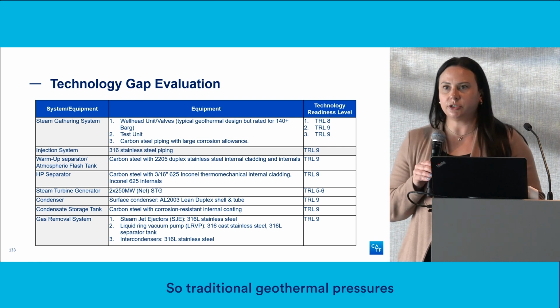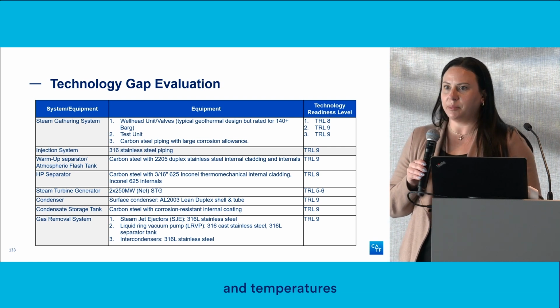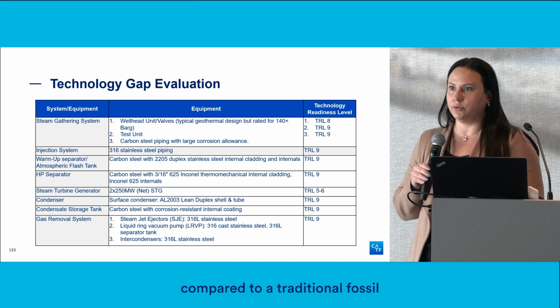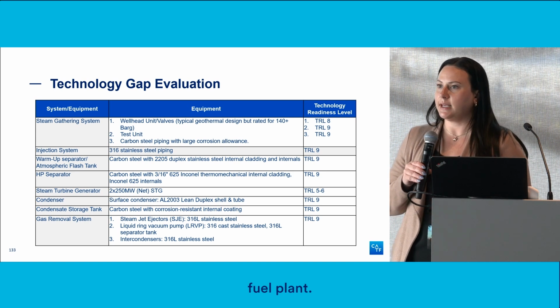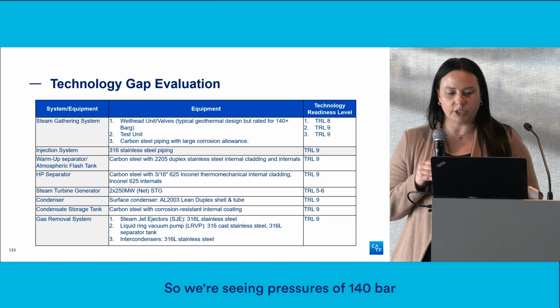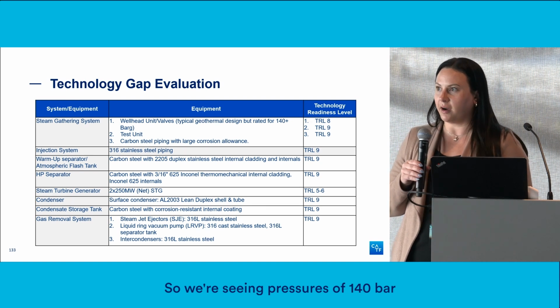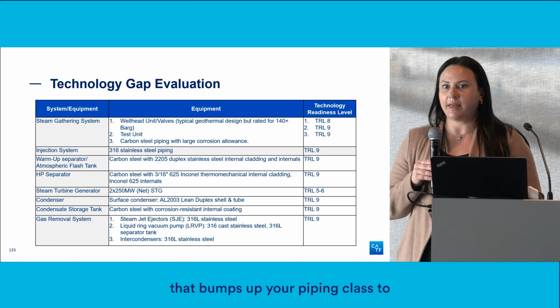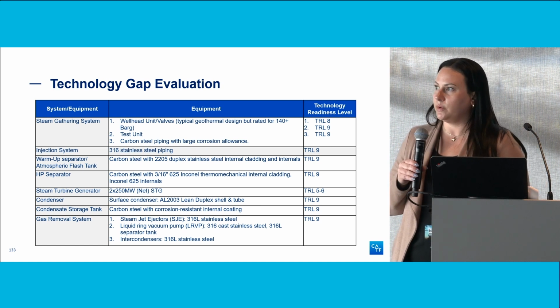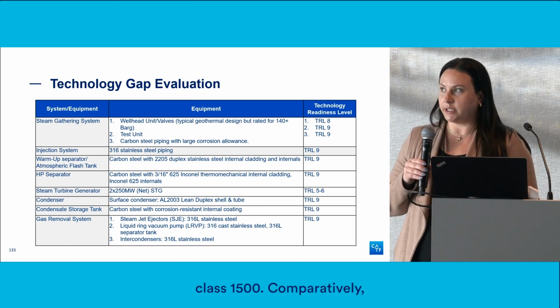Traditional geothermal pressures and temperatures are very low compared to a traditional fossil fuel plant. We're seeing pressures of 140 bar at 400 degrees C, which bumps up your piping class to class 1500.